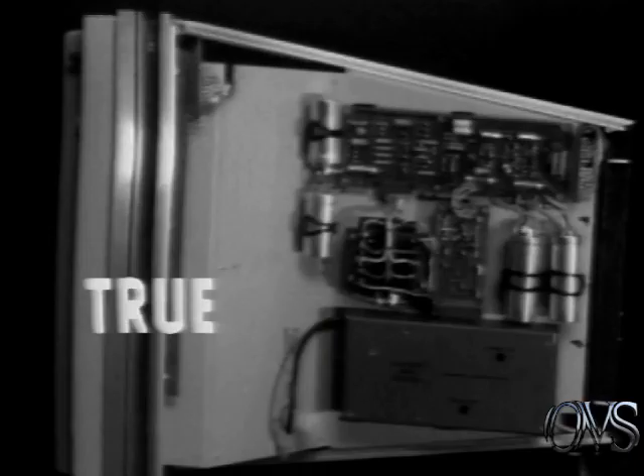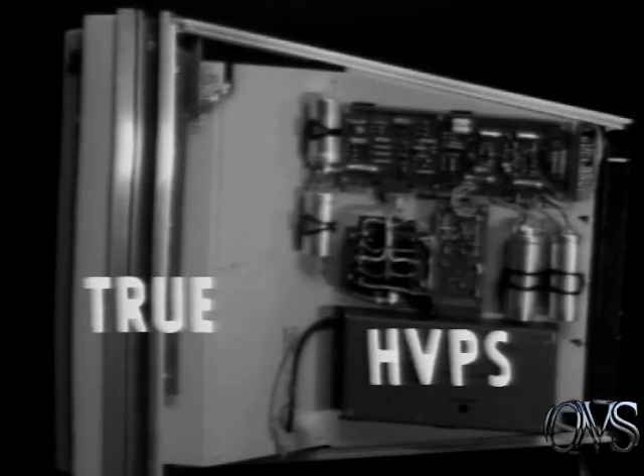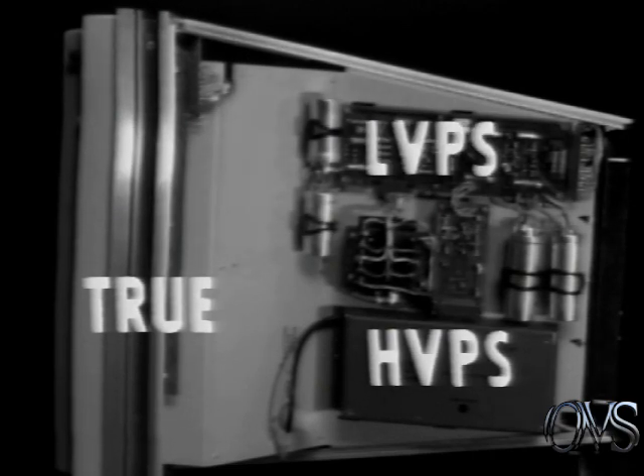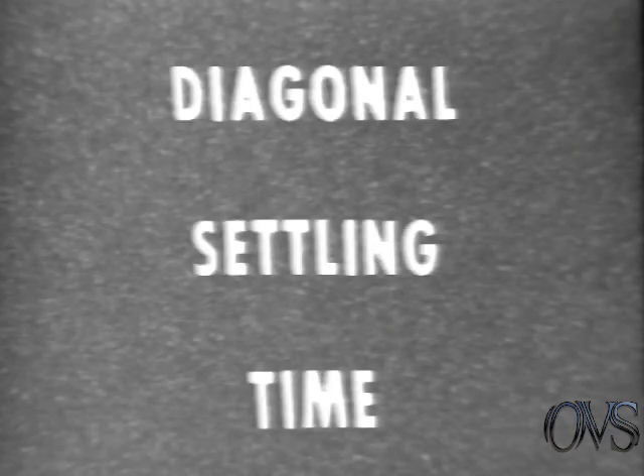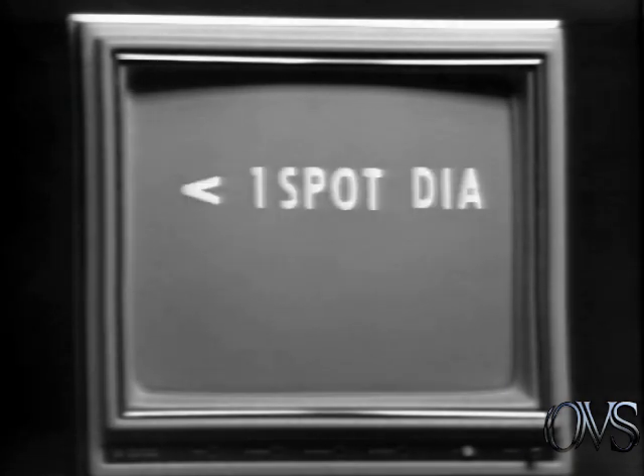You should have answered true. The high voltage power supply is dependent on the low voltage power supply for its operating voltages. Last question. What does the specification diagonal settling time or large step settling time refer to? This spec means that for any given deflection command, the spot will always be within one spot diameter of its final location in less than 1 microsecond.